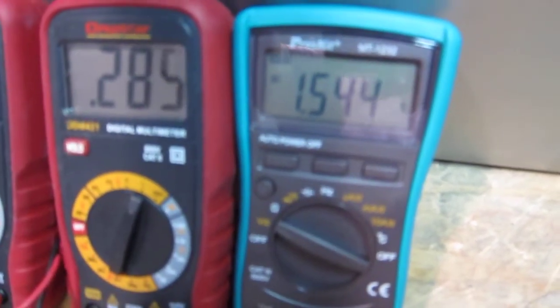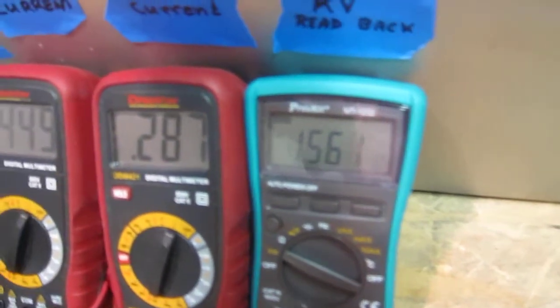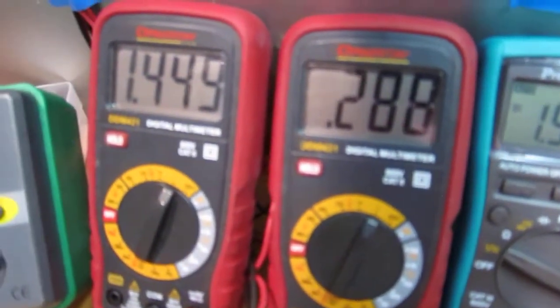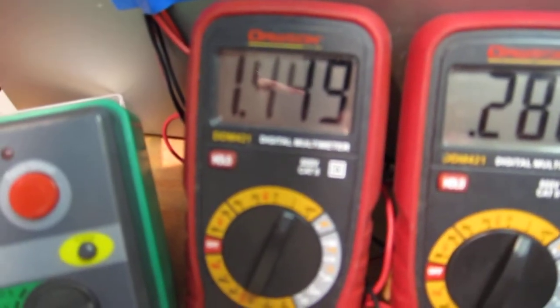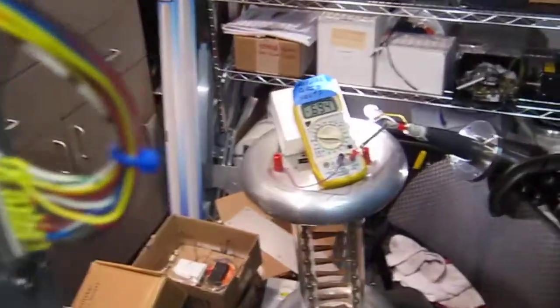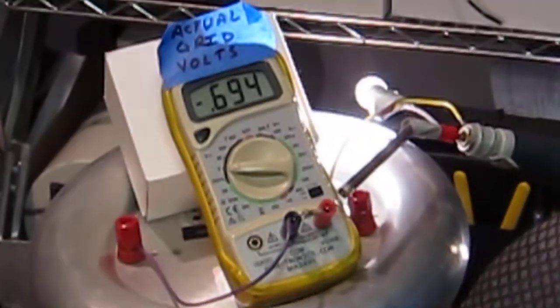There I'm at 22 kilovolts. And turn it up a little bit more, and you can see over here, this is the reading that needs to be scaled by the software, and that would be the high voltage output. There's the tube voltage. There's approximately 1.5 amperes flowing through the filament of that light bulb, and you can see the grid voltage is still there, the light bulb is still lit up.